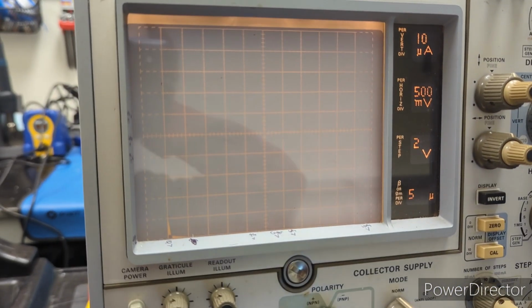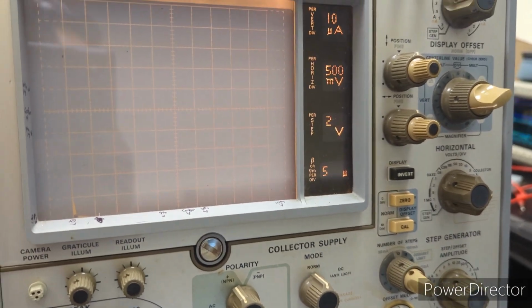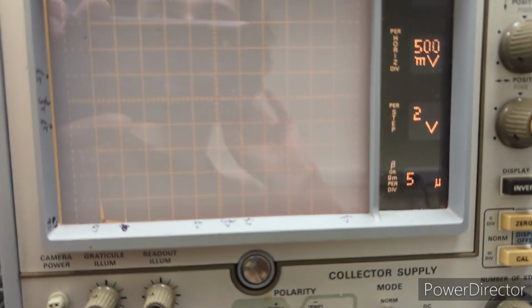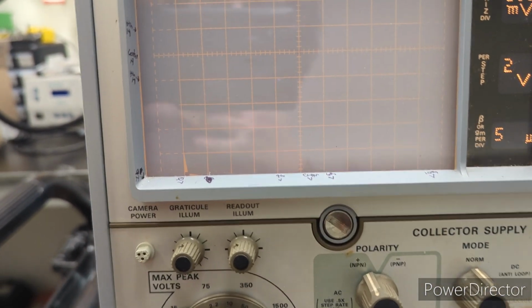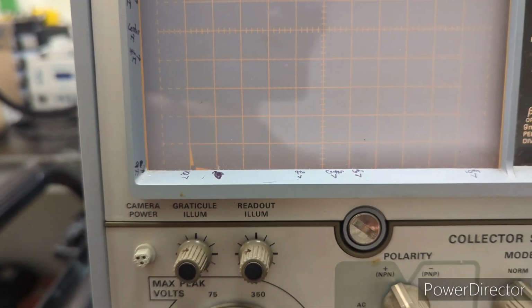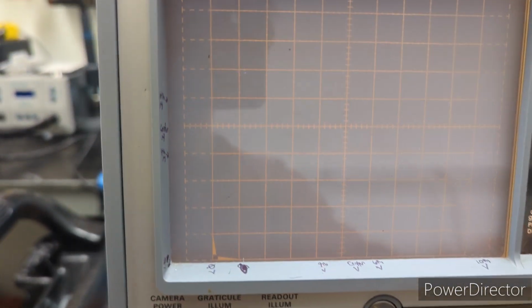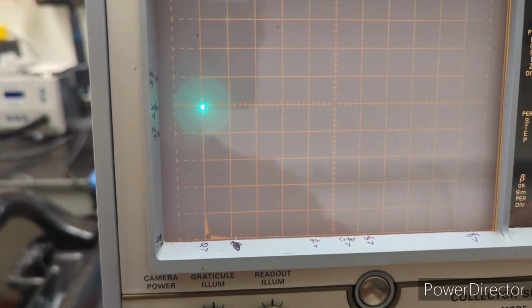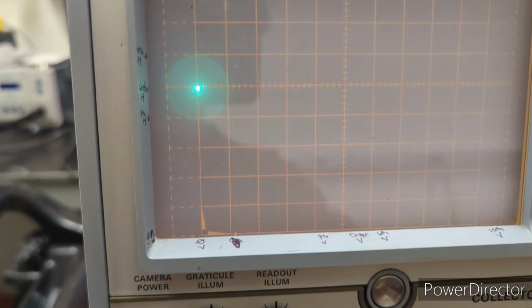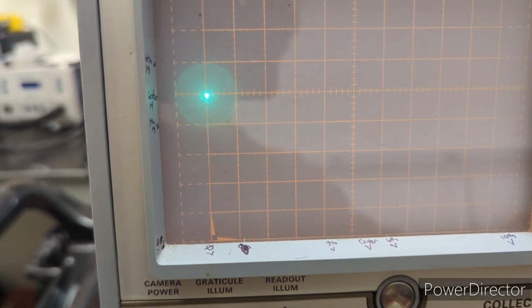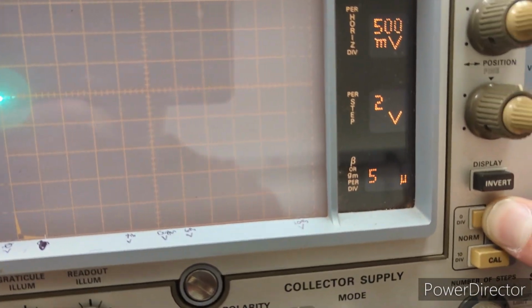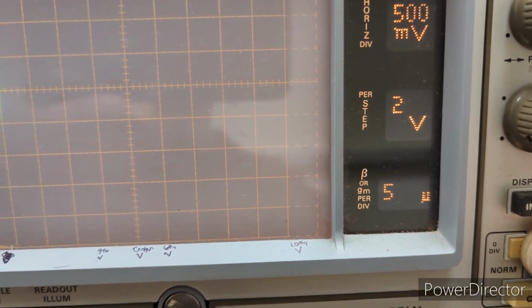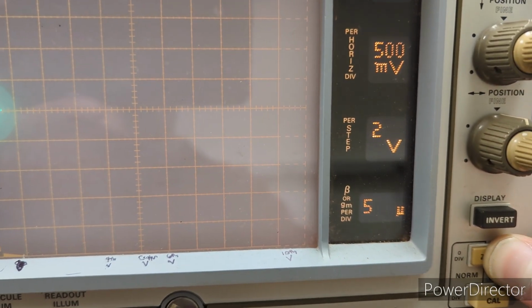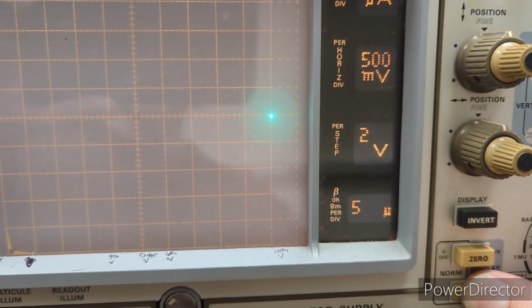All right, so this step is actually adjusting the vertical display amplifier gain, but it also can tell you a little bit about the horizontal amplifiers as well, to make sure they are calibrated correctly. So for example, now just pressing the 0 button, that is where the trace should be on the 0 vertical graticule and the center horizontal graticule, and then pressing the cal button should bring it all the way to the 10th vertical graticule. So yep, we should see it here.